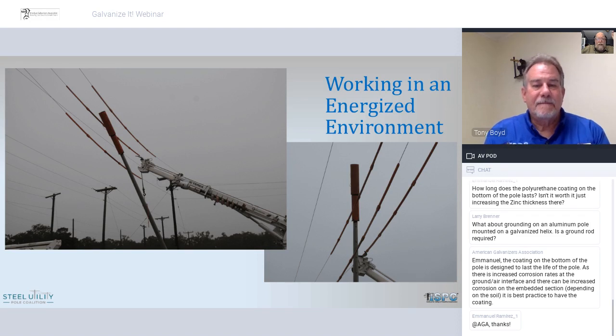Grounding of the pole during setting is an important consideration, because grounding of the pole during setting will ensure that the voltage applied to the pole is going to remain very low. That's the phenomenon that occurs when you ground, is that you collapse the voltage. Current will still flow, but the voltage collapses. And then a voltage would be created between the pole and a gap that occurs between the pole and the earth. That's why the lineman wears gloves. So even if you're setting a steel pole in a 115 kV circuit or a 230 kV circuit, those class 2 gloves, even though they're only rated at 20,000 volts, will provide a level of protection if you ground the pole. So grounding the pole is the hard part.